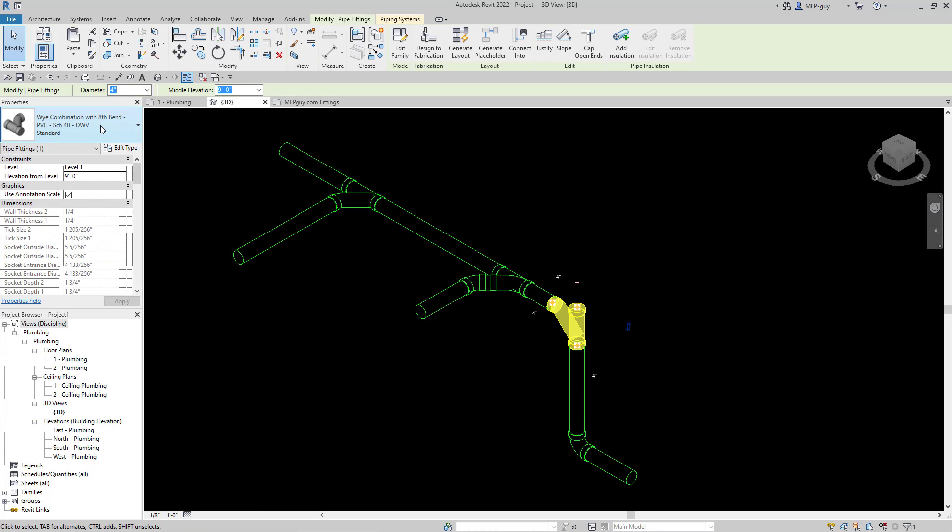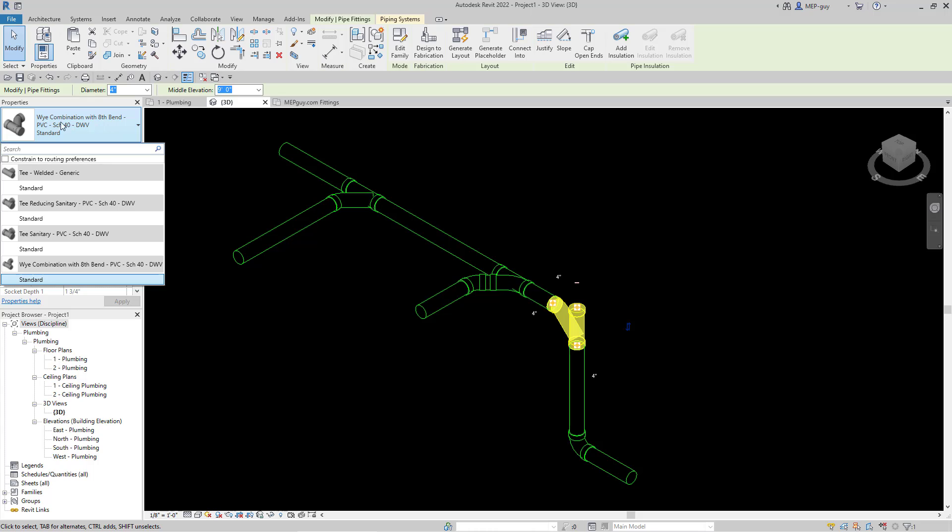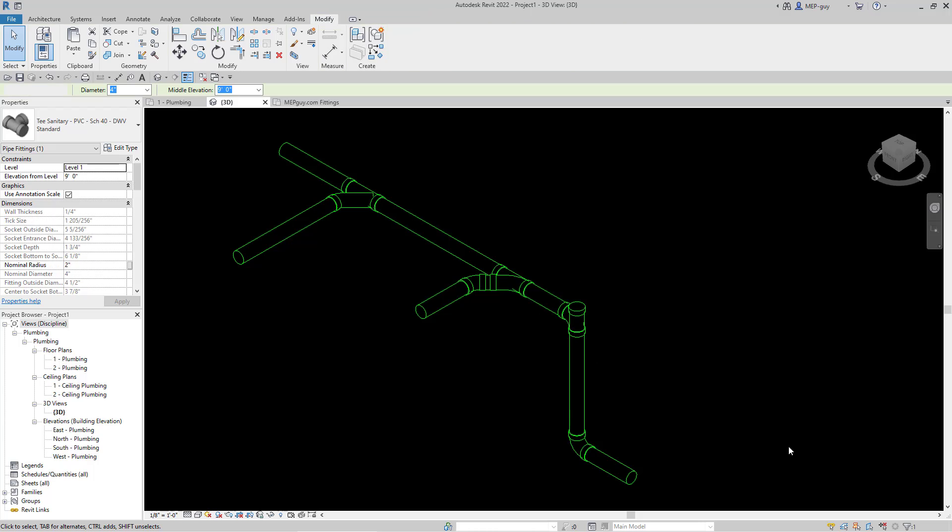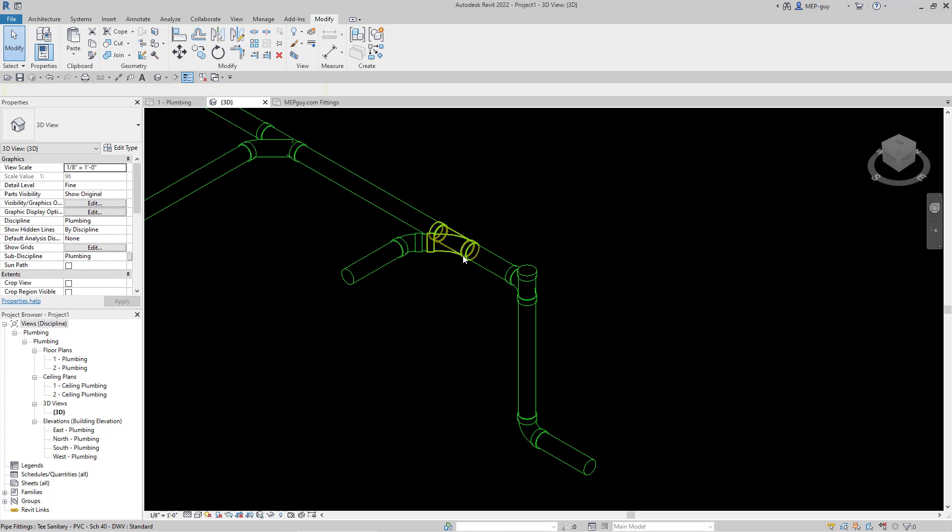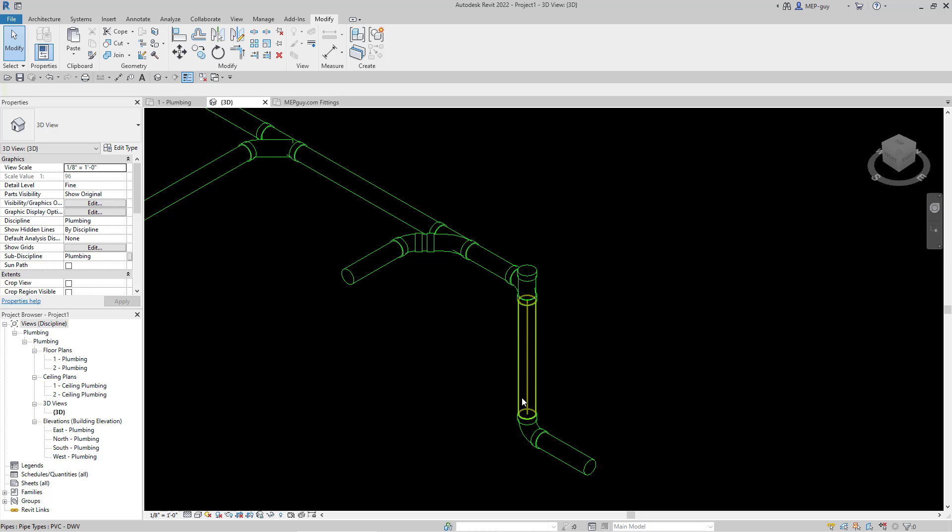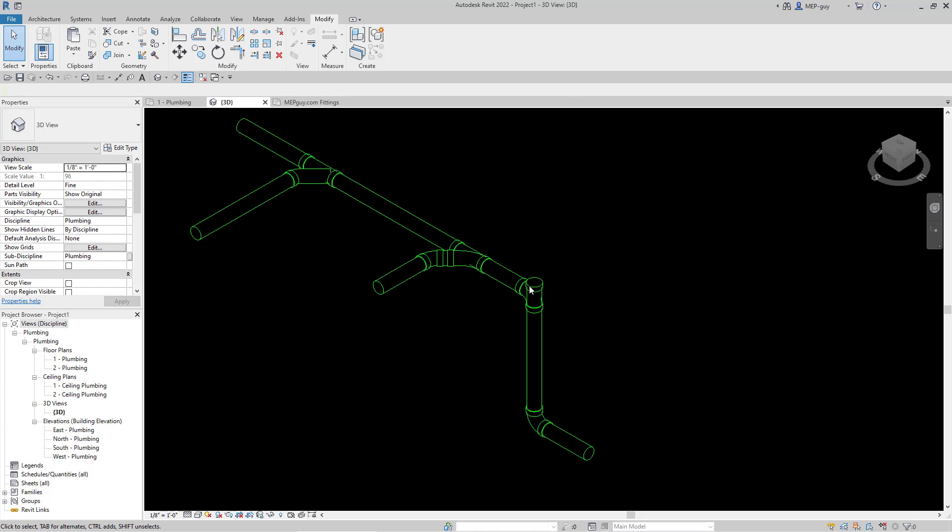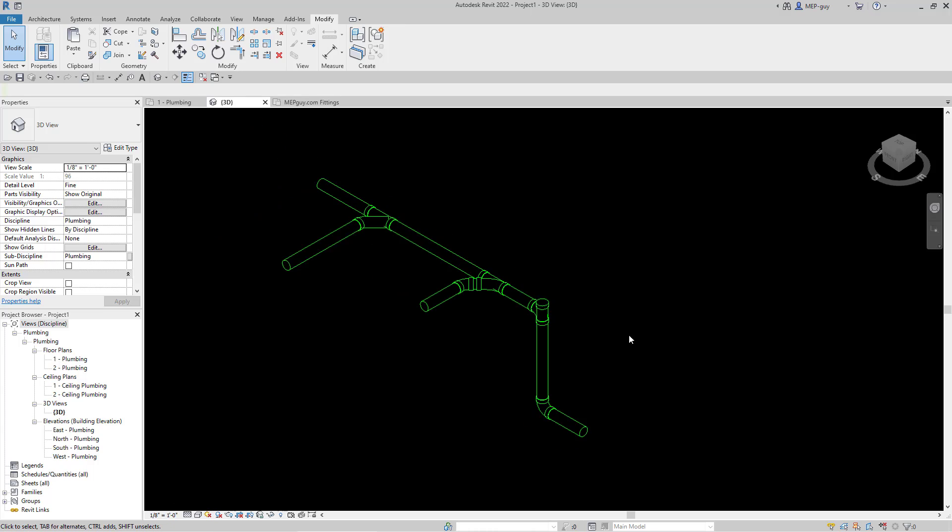So now to change it back, I can just hit my dropdown. And we can just go to my sanitary T right here. And that is perfectly code compliant. Because now we have gravity that's helping us get to this vertical drain. And so there's nothing wrong with doing this.